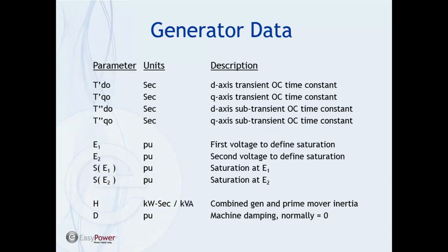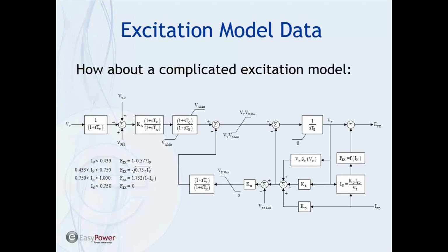It used to be just, give me one single Thevenin value that represents the short circuit capability. That's what we do for ANSI fault calculations. Well, it gets a tad bit more complicated here because we want to simulate the real-time behavior. And then not only those, but now we have saturation and inertia. It just gets even more complicated.